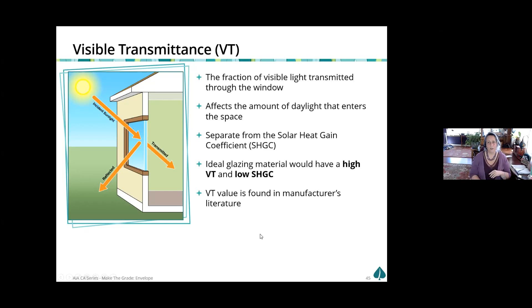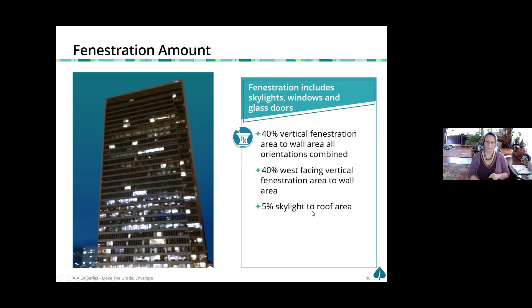Fenestration amount does depend on orientation or azimuth. For these building types, we get 40% window-to-wall ratio. It has nothing to do with conditioned floor area now, it's about how much exterior wall you have and how much of that is window. And it's vision glass, not spandrel, by the way, spandrel is considered an opaque surface. You get 40% of that entire wall area, all four orientations combined. You cannot exceed 40% on just your west elevation, and you cannot exceed 5% skylight-to-roof ratio.